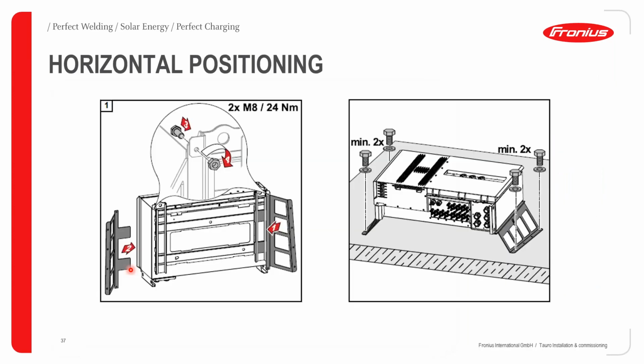If you do choose to mount your Tauro horizontally, you will need to purchase the handles, okay, which is not included as standard with the Tauro. It is an additional extra, okay, but this will then enable you to mount your Tauro flat on the ground. And when you do this, the Tauro itself comes with these slots that these mounting brackets will go into, and from that you can then mount it on the floor. Remember, these mounting brackets can also be used to lift the inverter. As you can see, we have slots for hands, and this will just allow you to also mount your inverter much easier if you are going to mount your inverter vertically.